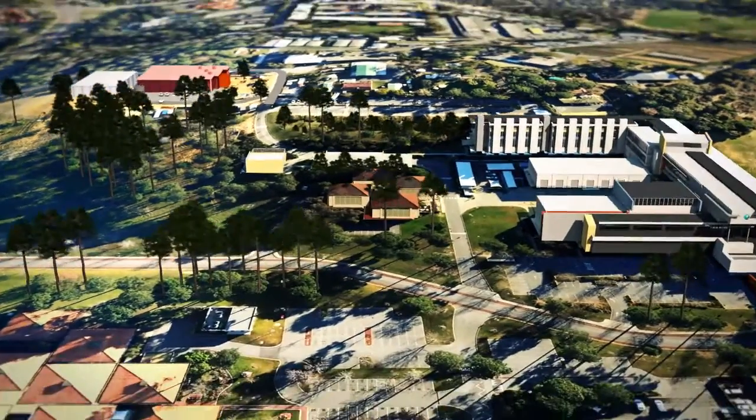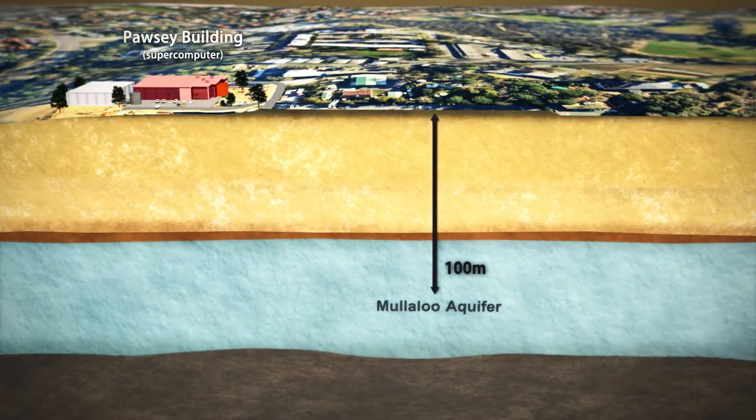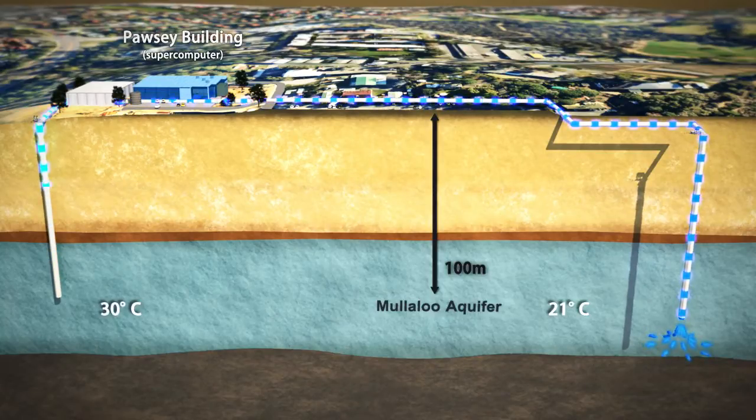The groundwater cooling system works by accessing water from a depth of around 100 metres from the Mullaloo Aquifer, located beneath the Pawsey Building. This groundwater has an ambient temperature of around 21 degrees Celsius. The water is pumped through an above-ground heat exchanger to cool the supercomputer, and the heated groundwater is then returned to the same aquifer via downstream reinjection.